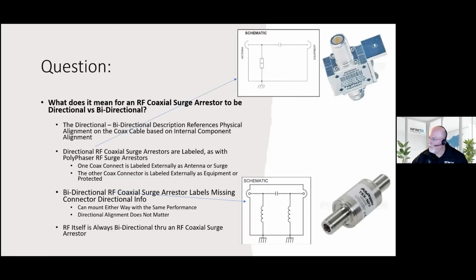What does it mean for RF coaxial surge arrestors to be directional or bidirectional? That's a great question. With RF surge arrestors, the RF direction is always bidirectional, but these terms are referring to physical alignment on the coax cable. With PolyPhaser products, you'll see one connector labeled antenna, or it might say surge, on the external label, and at the other connector, it'll say equipment or protected. This is a directional unit, as the schematic shows. We want the gas tube to be closer to the source of the surge. So that's why it's directional.